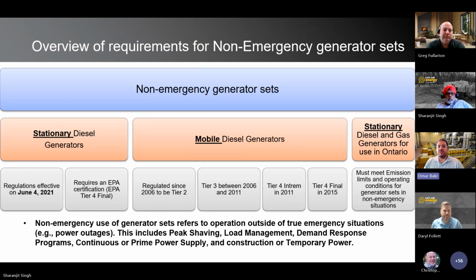So basically, when we talk about non-emergency generators, they cover a wide range of applications that are not under an emergency requirement. Non-emergency power refers to the use of the generator outside of emergency situations. This can include peak shaving, load management, demand response programs, prime or continuous applications, or even temporary power for construction. Sometimes people think temporary power for construction can have an exemption, but this is not true.